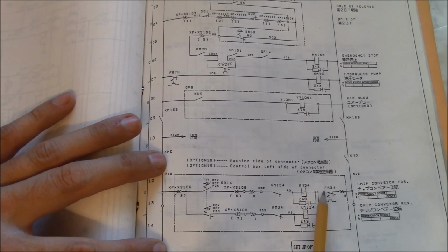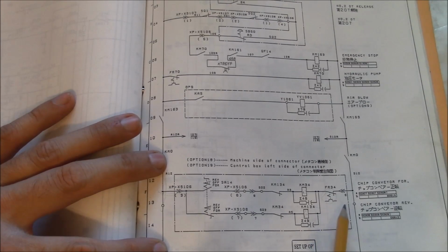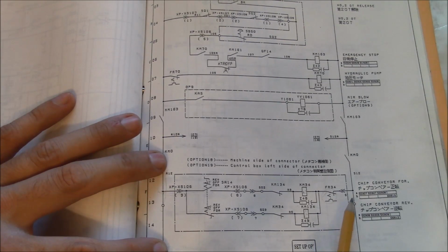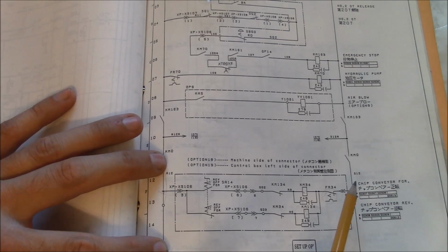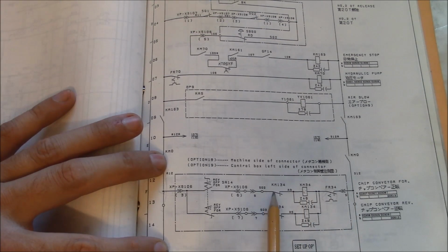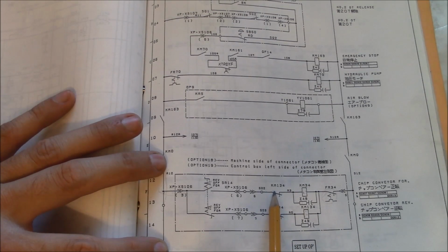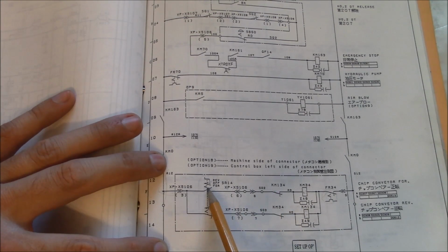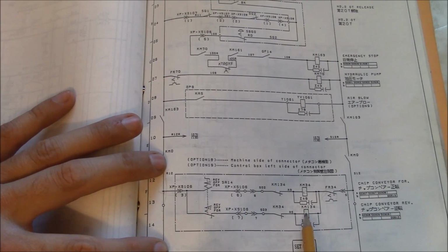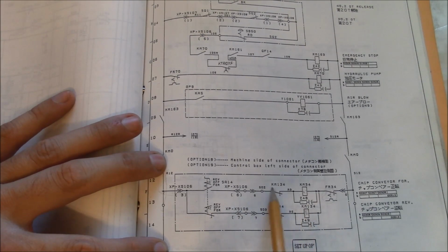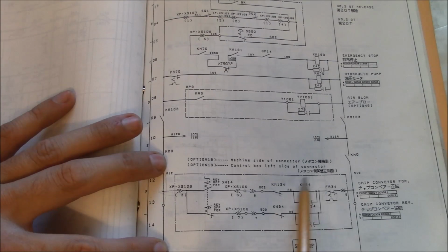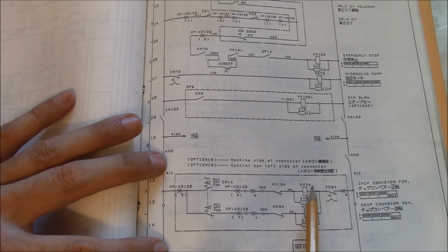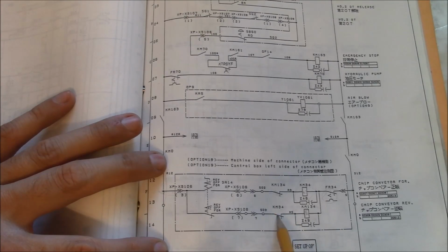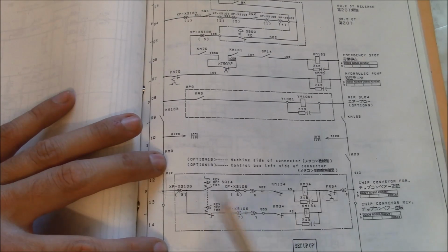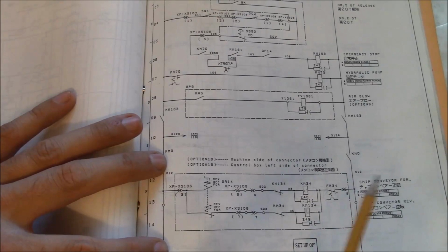This is probably some kind of safety switch, like an e-stop switch. But if you look, the circuit has to go through KM134, which is a normally closed contact. So if you try to turn the conveyor on to forward while the KM134 coil is on, that contact would be open and it wouldn't be able to turn on KM34. So this is both an electrical interlock and a mechanical interlock within the switch.